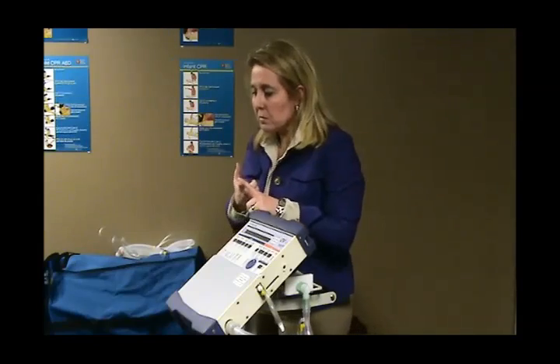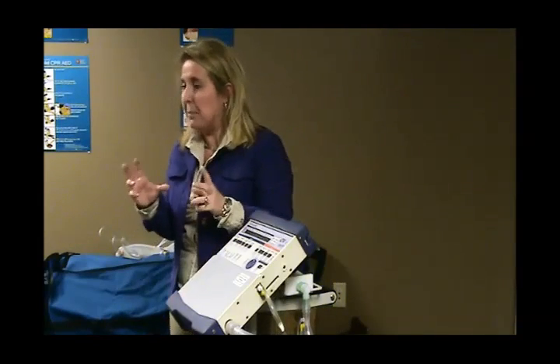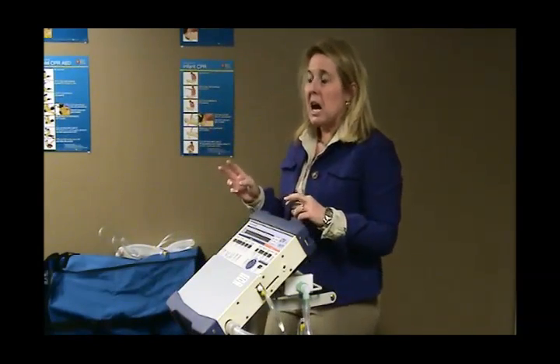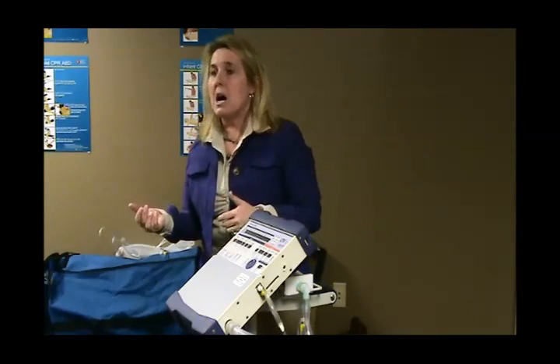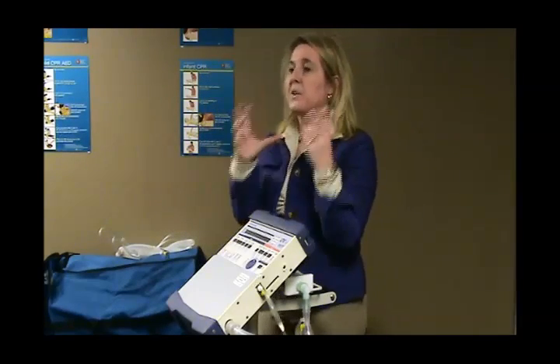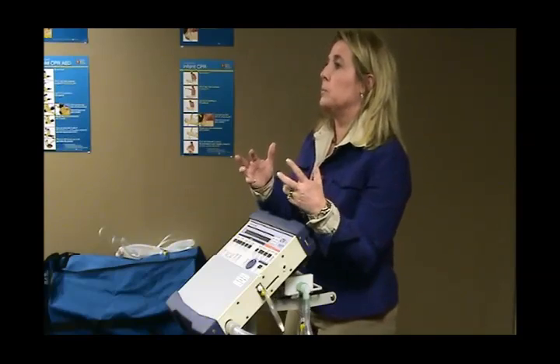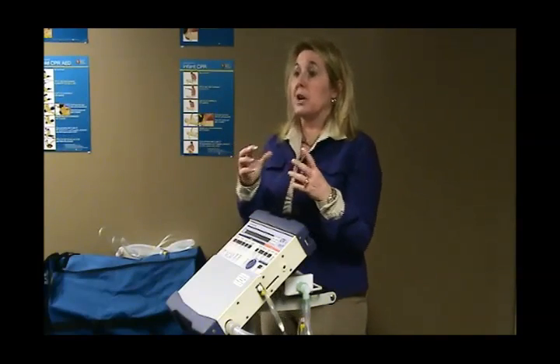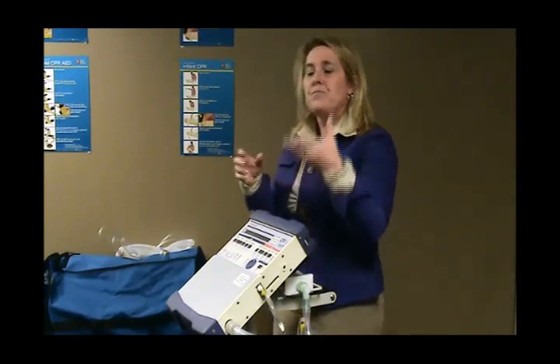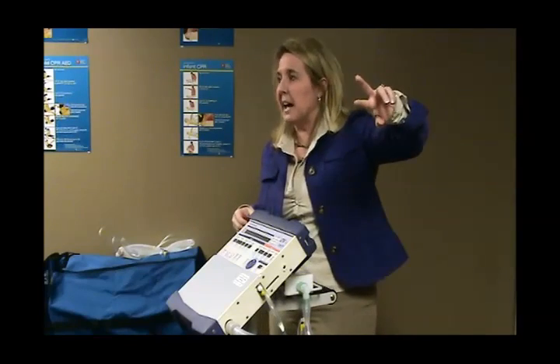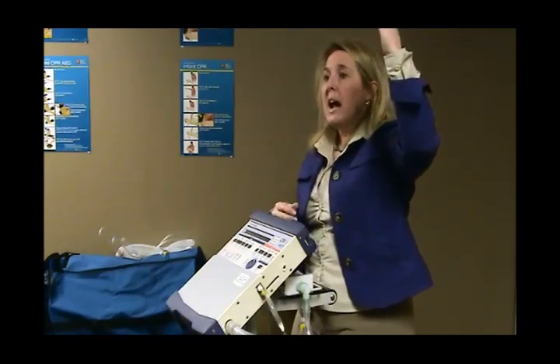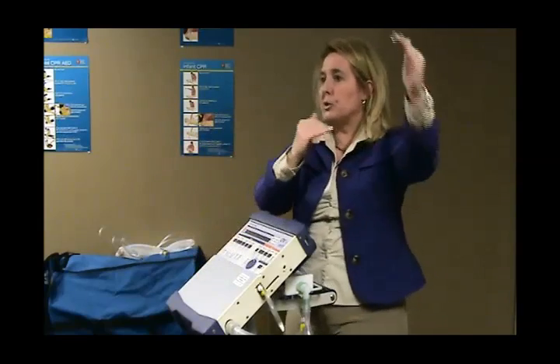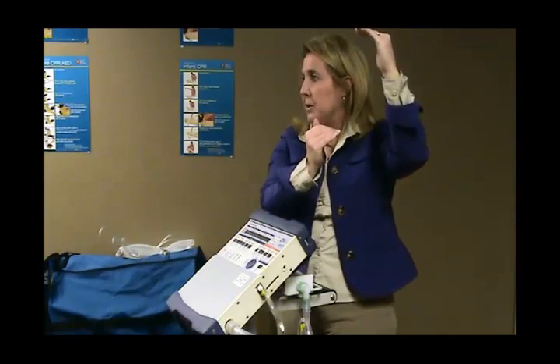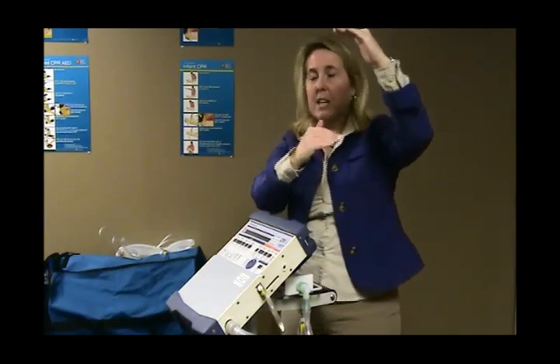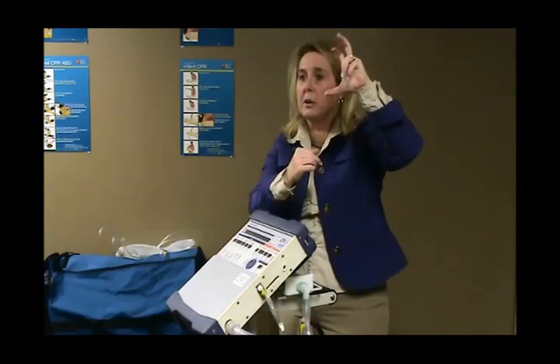The second type of breath that we can give is a pressure breath. And with a pressure breath, this time instead of giving a fixed volume with each one of those machine breaths or assisted breaths, we're going to give a certain pressure. So it's sort of the converse of what we just looked at. We're going to give a certain pressure, and with our ventilator, that pressure is over the top of PEEP. Okay? So we'll revisit that here in a second. But let's say it's 15 centimeters of water pressure with a PEEP of 5.